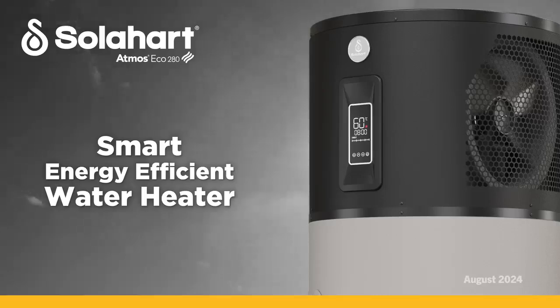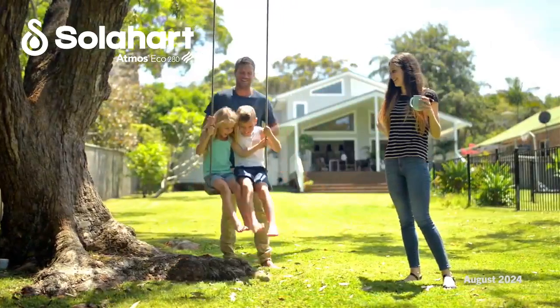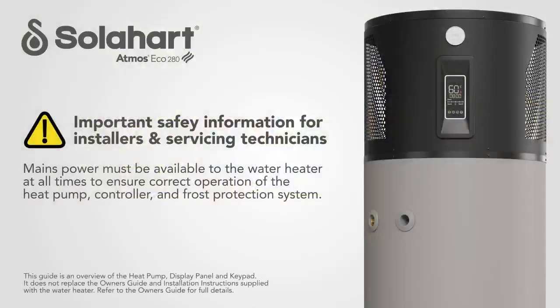Atmos Eco is a highly efficient heat pump water heater designed to provide continuous, renewable hot water to meet the needs of medium to large families. Mains power must be available to the water heater at all times to ensure correct operation of the heat pump, controller, and frost protection system.